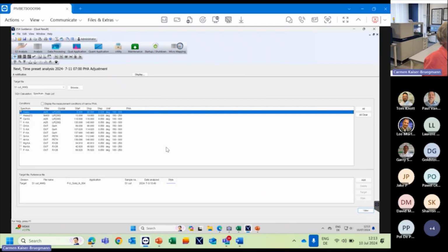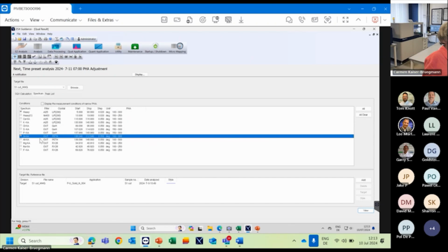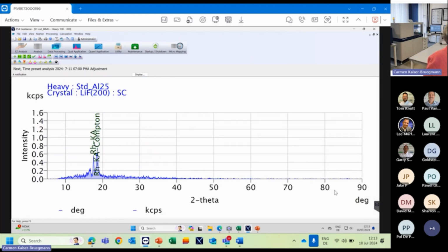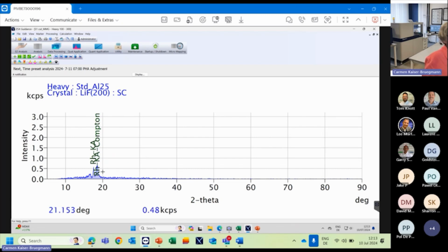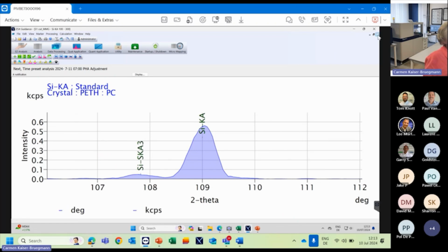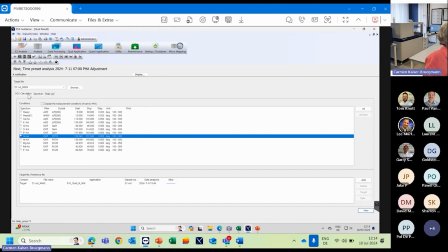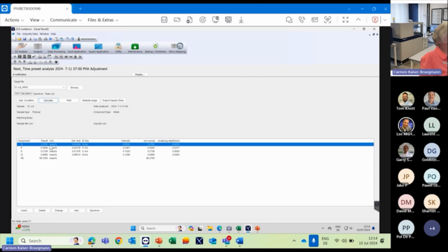So here you can see, for example, an example of some of the spectra. I won't look at all of them, but they are divided into heavy spectra and light spectra. I think the sample contains silica, so we can have a look at the silica. So yeah, that's an example of the heavy element spectra. Because it's a light matrix, we have a bigger Compton peak. Here we have the silica in the material. Yeah, so this is how we can have a look at our data. And what do we see from the calculation of the data? We have a result and we have a detection limit. So at all times, we always need to have a look at our detection limit and our analyzing depth. So this is very important in XRF, because very often the specimen that we measure could not be maybe thick enough. So we need to have an infinitely thick sample to measure. So this helps us to understand if our semi-quantitative result is good.